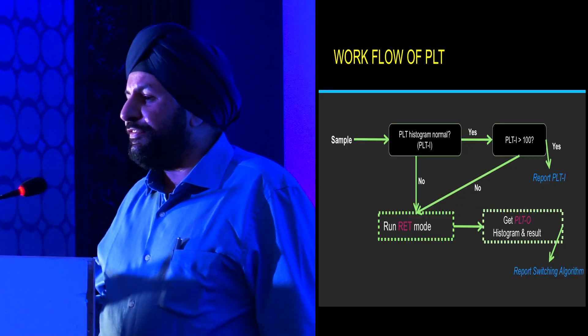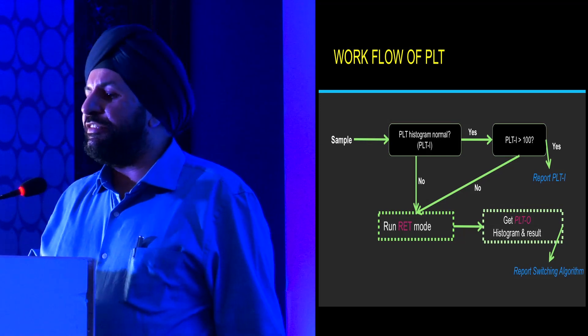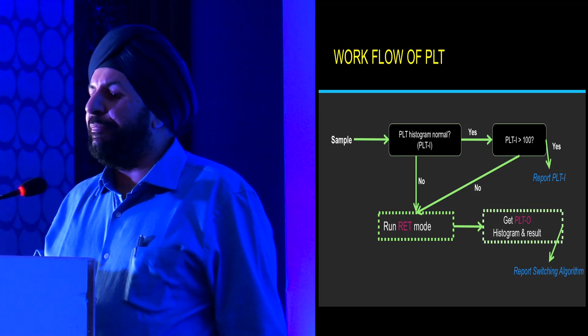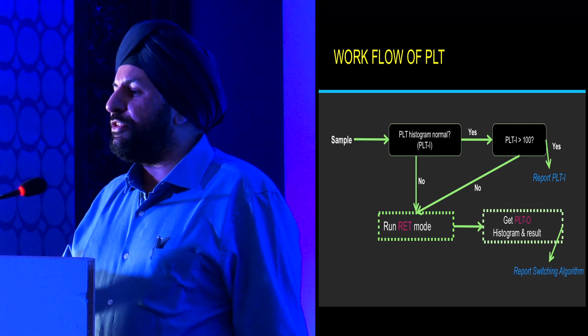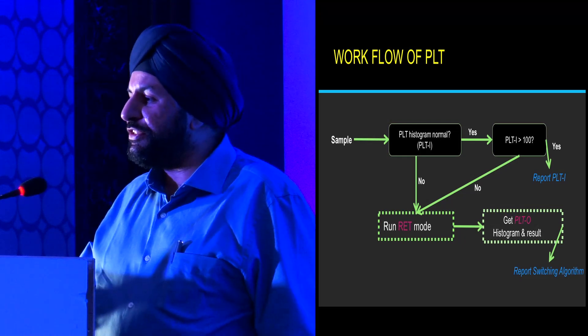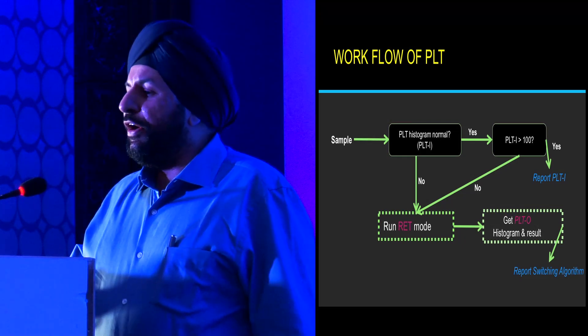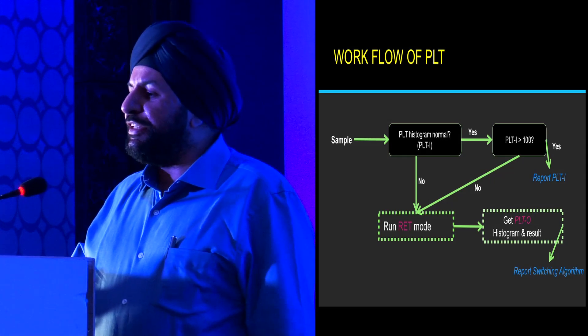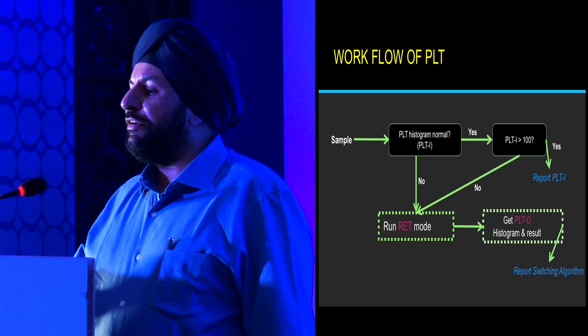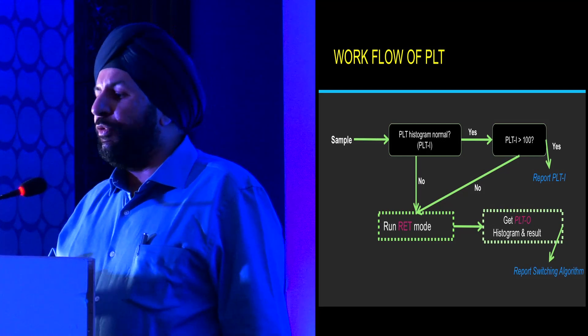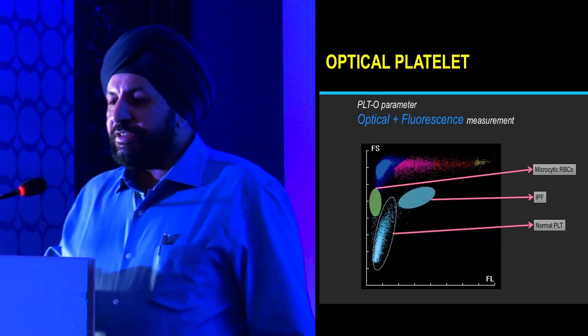This is the workflow of platelet counting as we do in our laboratory. All our platelets are subject to impedance-based counting first. If the platelet histogram is normal and the count is more than one lakh, we just report the impedance platelets as is. However, if the platelet histogram is abnormal or the platelet count is less than one lakh, we run the platelet in optical platelet mode and let the switching algorithm take over.